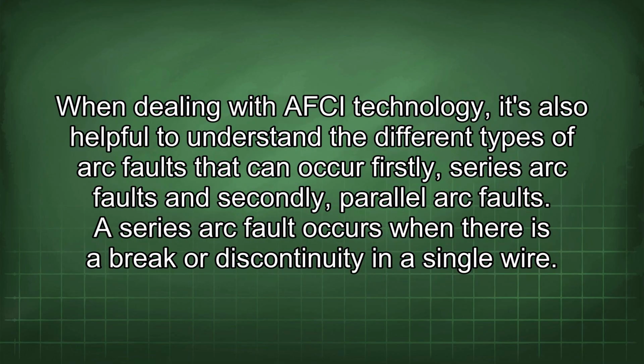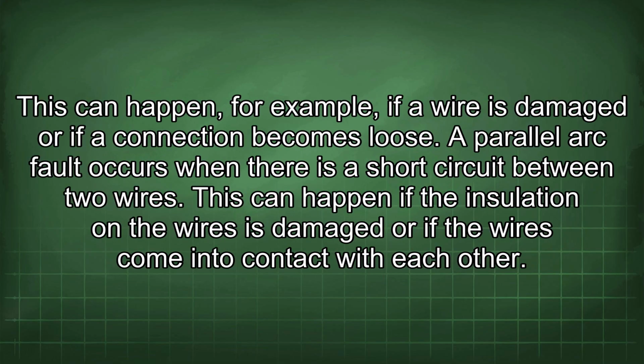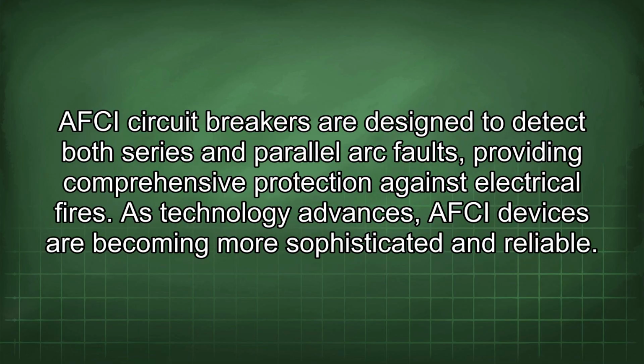When dealing with AFCI technology, it's also helpful to understand the different types of arc faults that can occur. Firstly, series arc faults, and secondly, parallel arc faults. A series arc fault occurs when there is a break or discontinuity in a single wire. This can happen, for example, if a wire is damaged or if a connection becomes loose. A parallel arc fault occurs when there is a short circuit between two wires. This can happen if the insulation on the wires is damaged or if the wires come into contact with each other. AFCI circuit breakers are designed to detect both series and parallel arc faults, providing comprehensive protection against electrical fires.